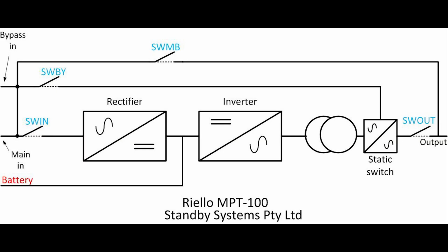Okay, here's a block diagram of the UPS. On the left-hand side are the main and bypass inputs. For applications that require two separate sources, a bus bar internal to the UPS can be removed that links the main input to the three-phase bypass input. For this presentation, the bus bar is in place, so the main in also feeds the bypass in. The main input power feeds the rectifier, which converts it to DC and powers the inverter, through to the transformer, through the static switch, and of course through to the output, our load.